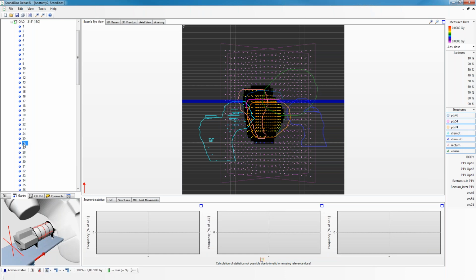This is a result of the fact that we are measuring dose pulse by pulse, which means that we can divide the measured dose into control points, and we can actually see what happens during each sequence of the treatment. So I can get a picture of the MLC positions during this control point and where the measured dose is.